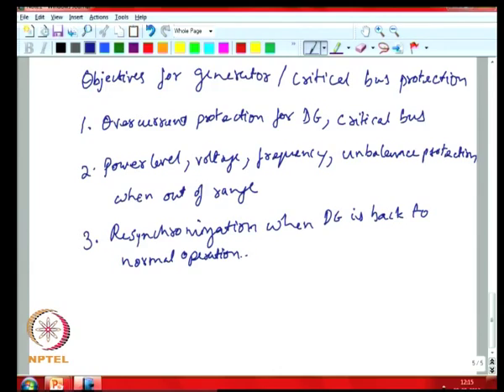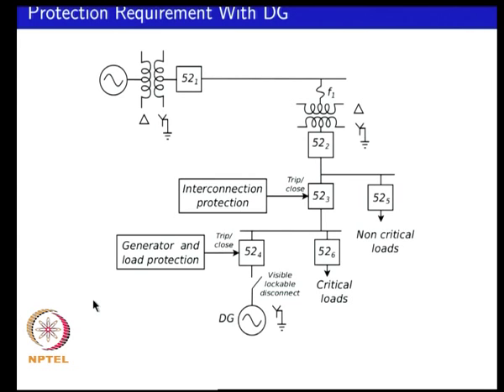After a shutdown, resynchronization may be important. Another important aspect is black start capability: if your system has gone down due to a blackout and interconnection breaker 52-3 is open, if you are able to start the DG you might close breaker 52-4 to provide a black start for your critical loads. So you might have critical load dead bus restoration as one of the requirements.